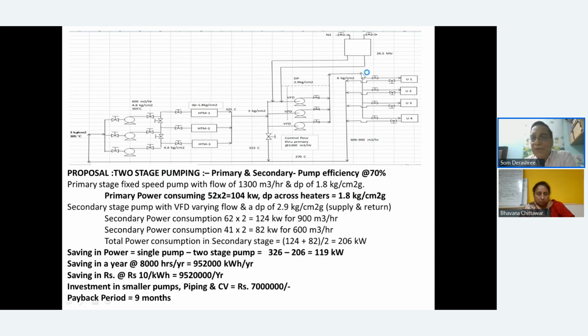And if you take this one, second line, this will go here, and then it will take this path, and again long. So all paths are equal, so that you don't have a problem of imbalances or unequal flow through all this. And whenever there's a lesser requirement of flow, there's a VFD here which senses back pressure and reduces the flow to this system as per the requirement.